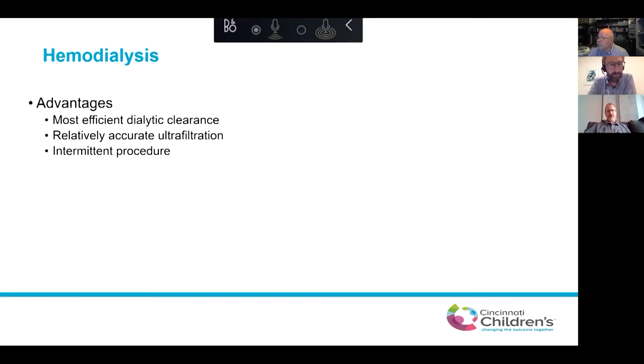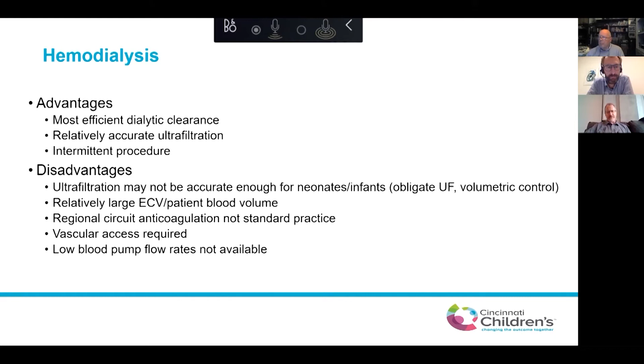All hemodialysis machines have some obligate ultrafiltration, which can be significant based on the size of a neonate, and the ultrafiltration is volumetric and not gravimetric. There's a relatively large extracorporeal volume to patient volume. Regional circuit anticoagulation is not the standard practice, so these neonates would be exposed to systemic heparin. Vascular access is required, and low blood pump flow rates are not available, which are important for small infants. Peritoneal dialysis has a number of advantages. Less technical expertise and resources are needed, so peritoneal dialysis can be performed easily in resource-strapped countries and environments.